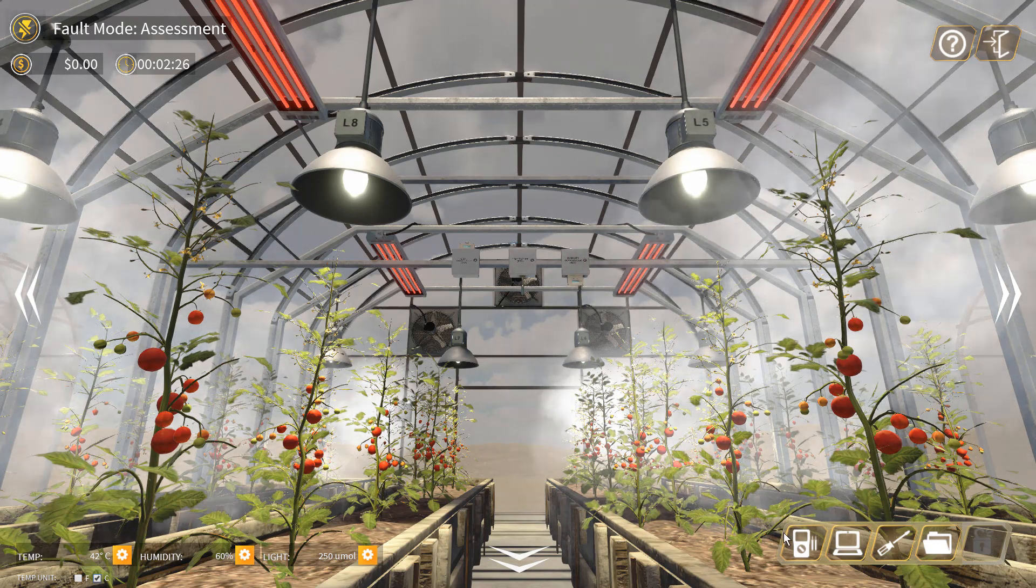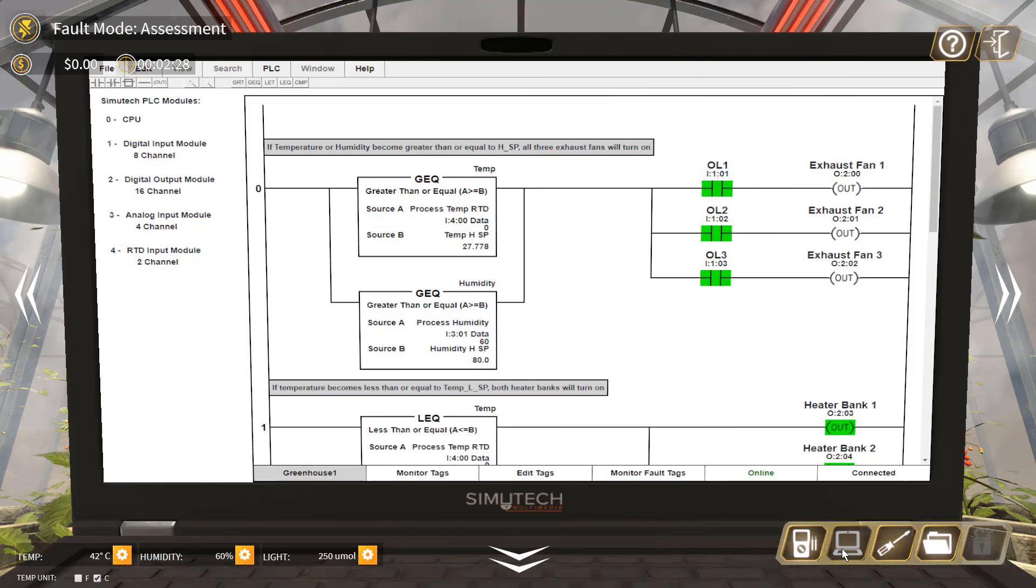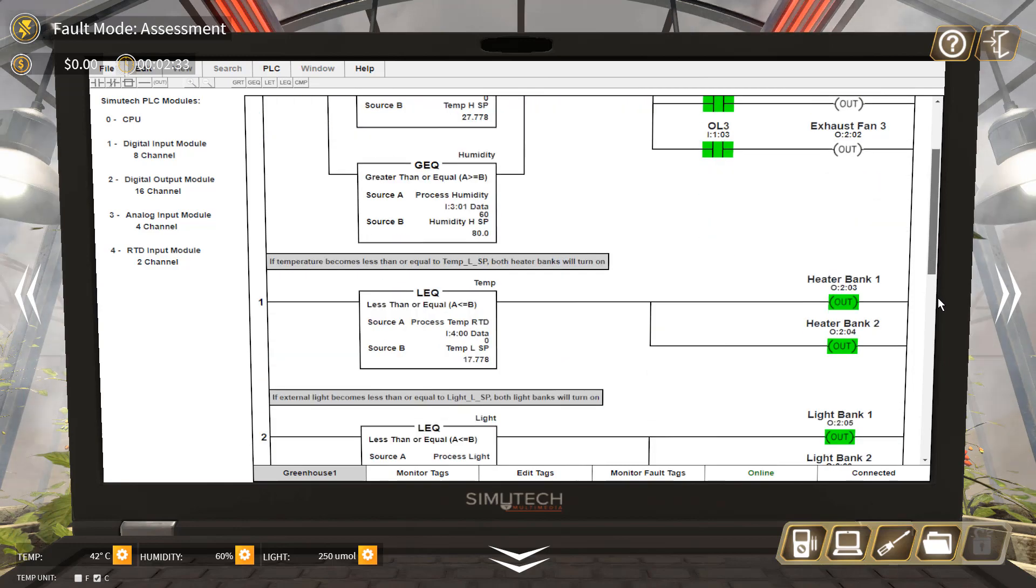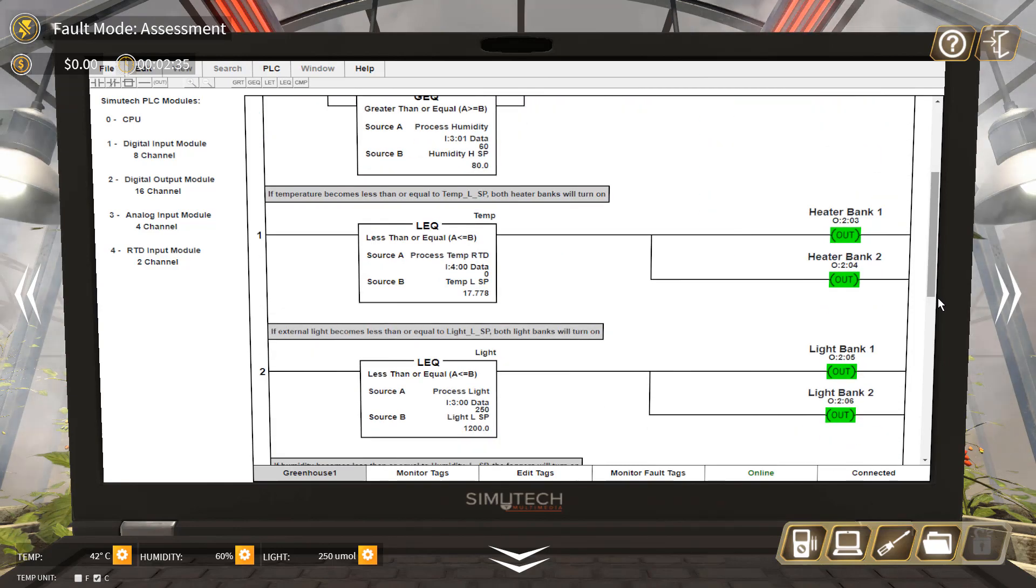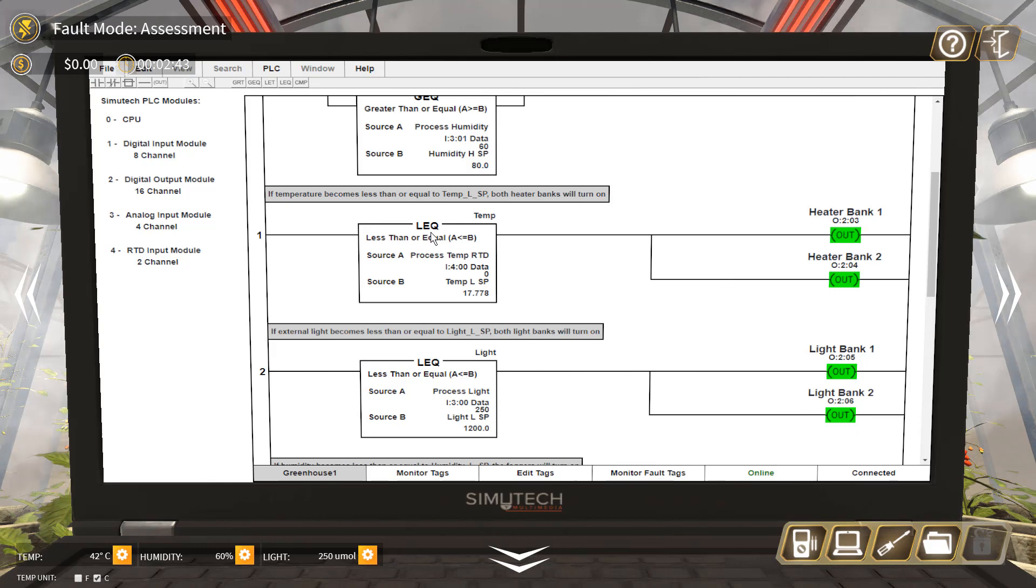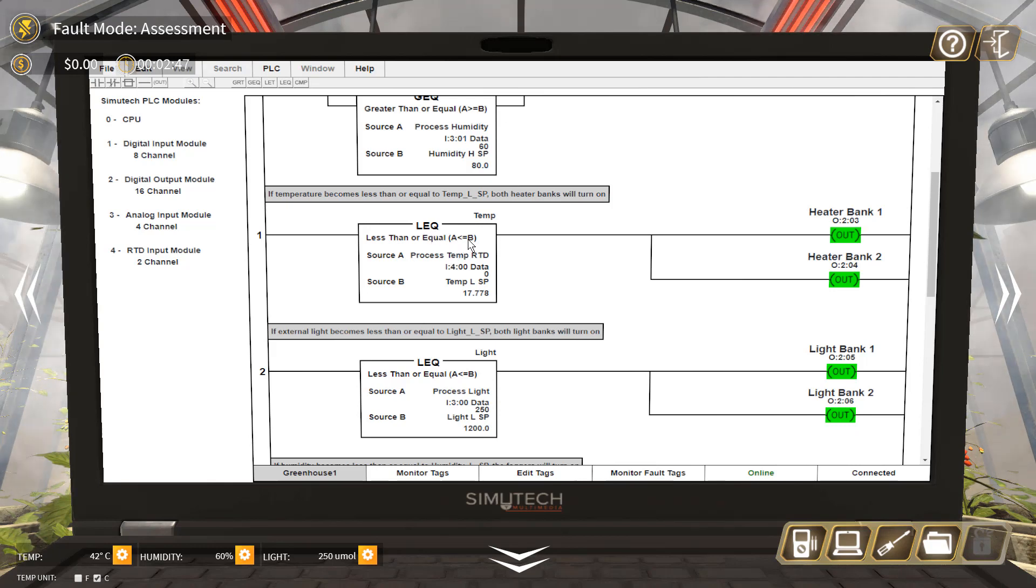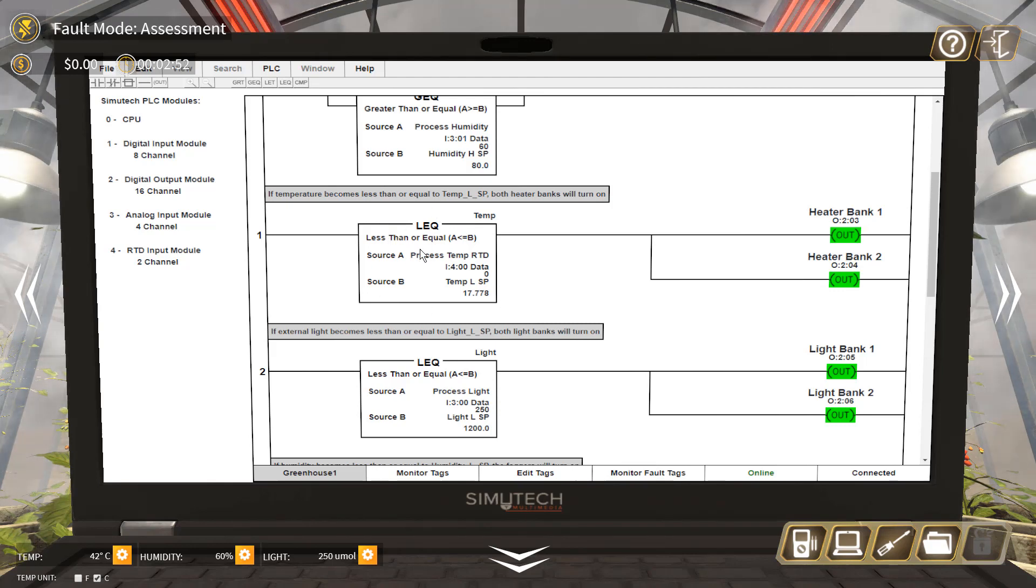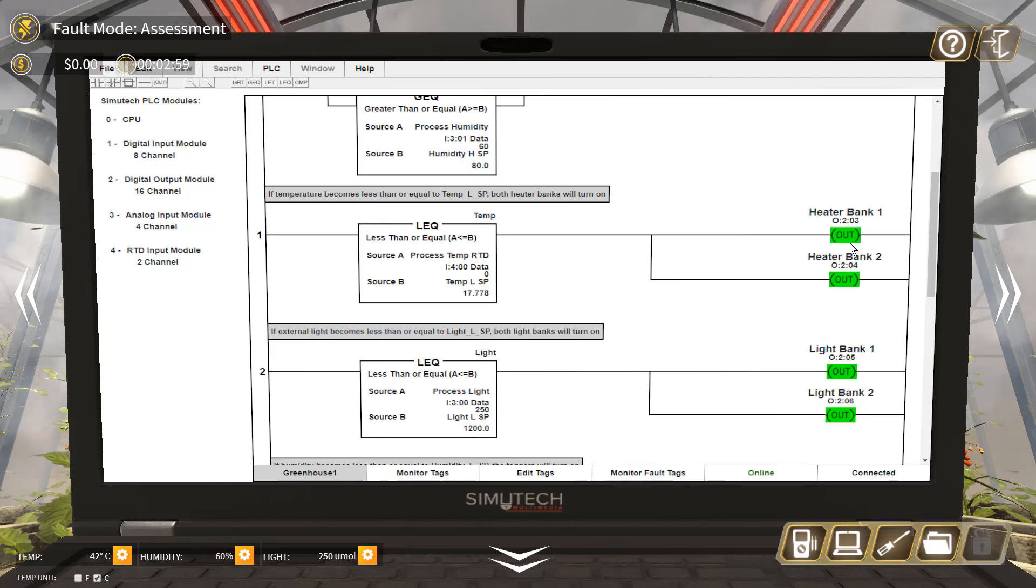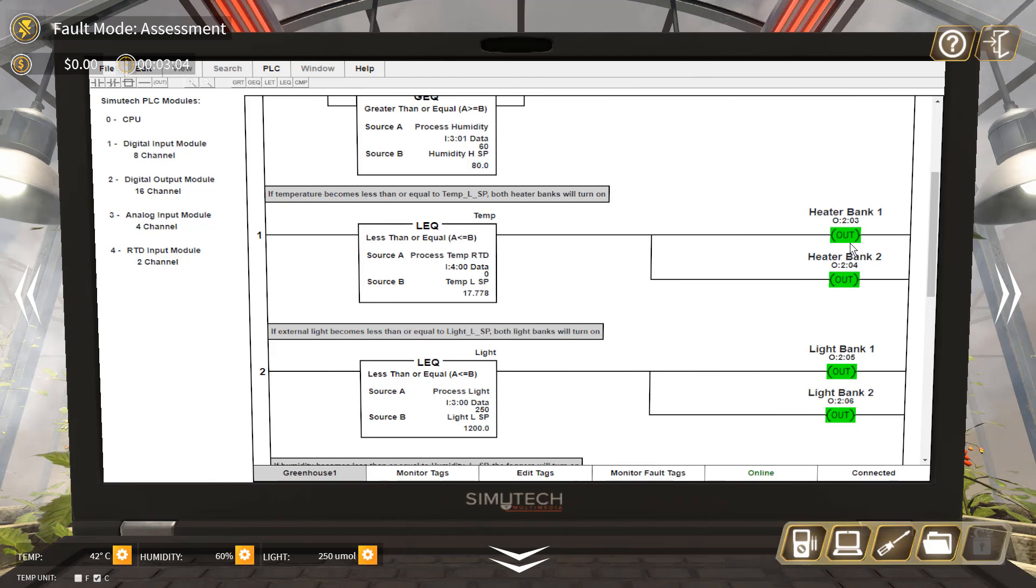If you have PLC access, you can go inside the PLC logic diagram to see what is wrong, which helps diagnose the problem. For example, this is a function block 'less than or equal'. If source A is less than or equal to B, then this function block is true and it will be energized. The virtual current can flow to energize both heater bank virtual output coil and task the PLC output channel normally open switch to close, and real current can flow to that circuit and energize the heater contactor coil relay.